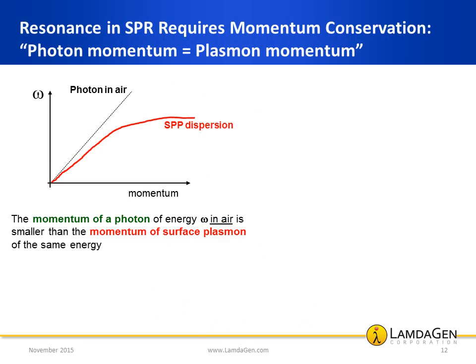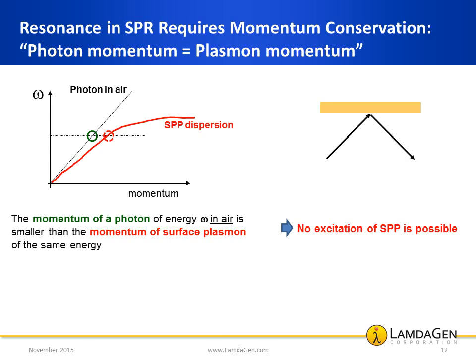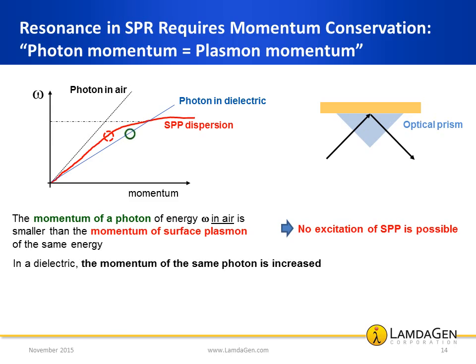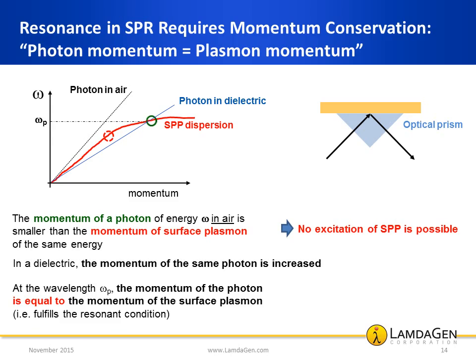In contrast, SPR has an additional and more stringent condition to fulfill its resonant condition: momentum conservation. The momentum of the impinging light in air is smaller than the momentum of the surface plasmon, so no excitation of surface plasmon is possible directly. To meet the resonant condition, the momentum of the light can be increased through adaptive optics, such as an optical prism. Therefore, for a certain wavelength, the momentum of the impinging light is modified to match the momentum of the surface plasmon, and a surface plasmon can then be launched. SPR requires the use of such adaptive optics to meet the resonant condition, which poses engineering challenges that will be discussed later.